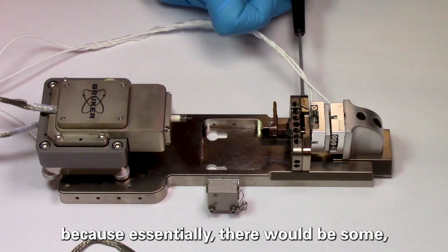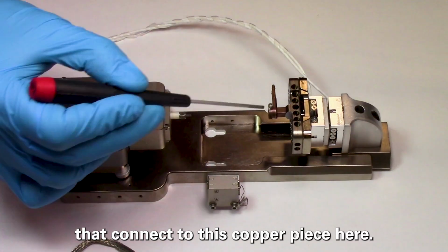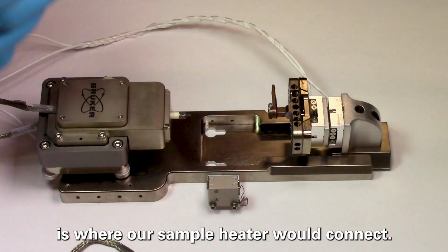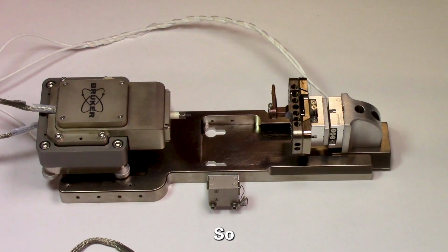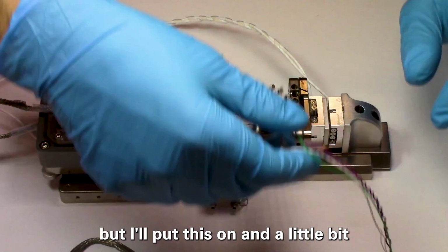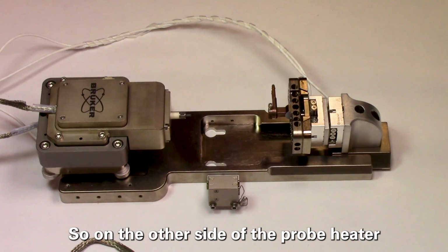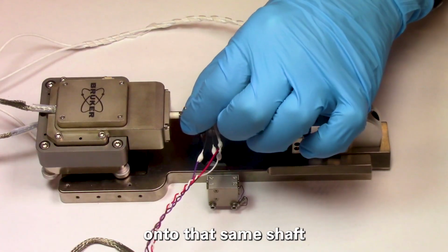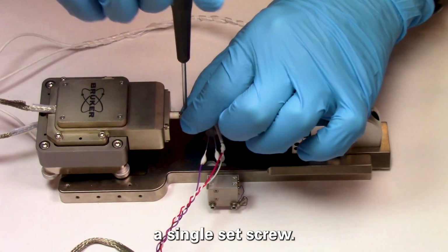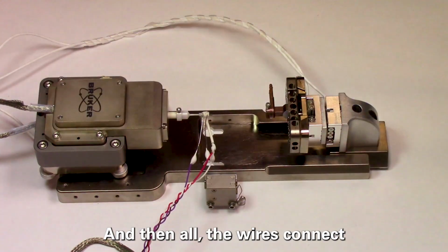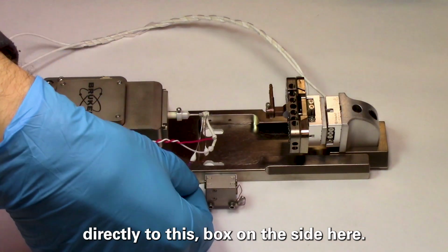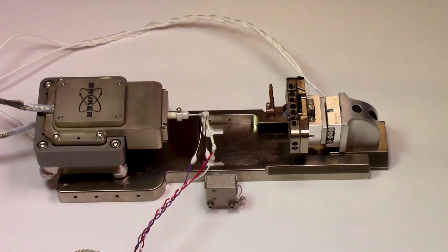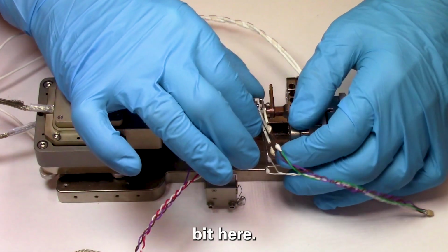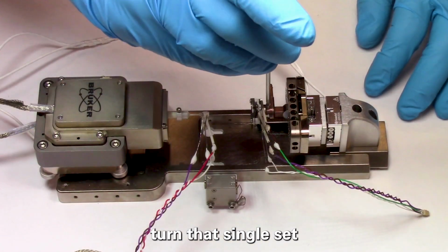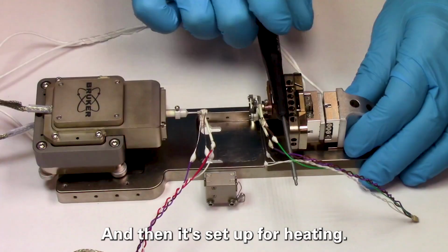But I say this is a dummy because essentially there would be some cooling tubes that connect to this copper piece here. But this piece here is where our sample heater would connect, so it would kind of just slide in right there, but I'll put this on in a little bit after I get the probe heater on. So on the other side, we'll put the probe heater onto that same shaft on the transducer. Again, a single set screw, so just slide it right onto that shaft. And then all the wires connect directly to this box on the side here. And now that the probe heater's on, we can put that sample heater on. So it slides just into the dovetail of this copper bit here, and then turn the single set screw to tighten it, and then it's set up for heating.